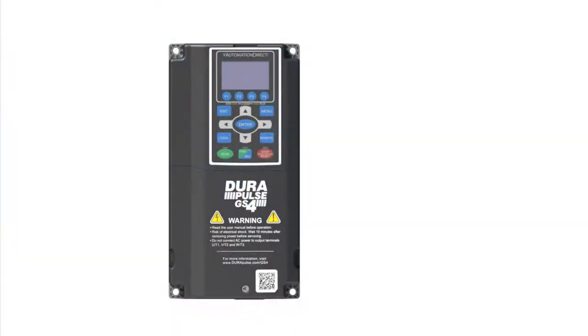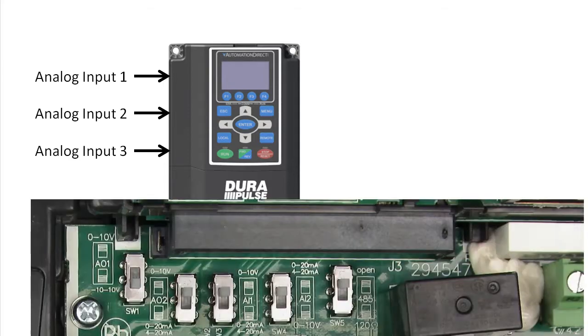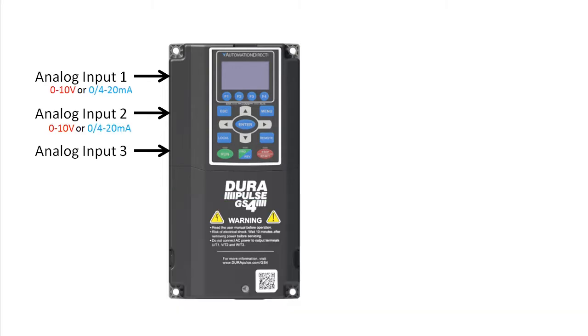All of the GS4 drives from AutomationDirect have 3 analog inputs. Analog inputs 1 and 2 have switches on a terminal board so you can switch them between current and voltage modes. Analog input 3 is a dedicated 10 volt input.